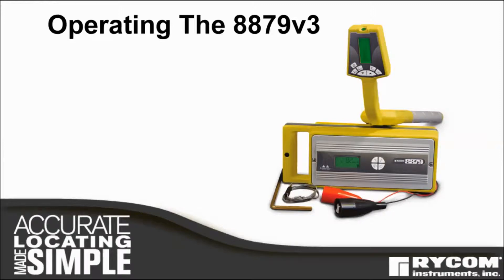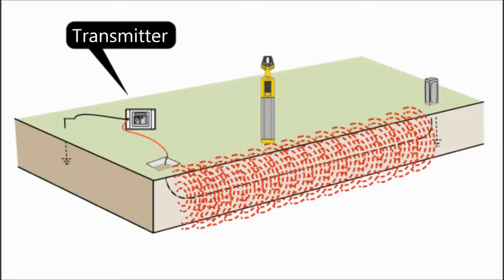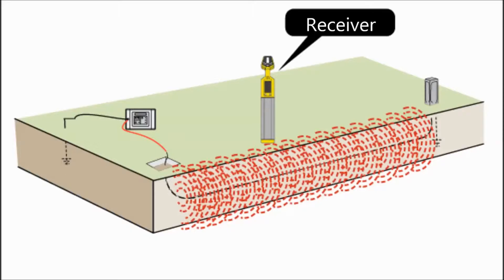This video will introduce you to the operation of the 8879 V3 cable and pipe locator. The basic principle of operation: a transmitter applies an electrical current to a buried conductor, then a receiver is used to detect the electromagnetic field radiating from the underground conductor.